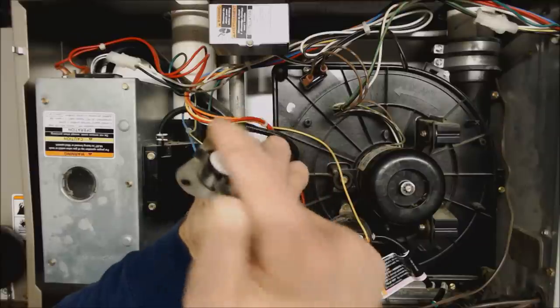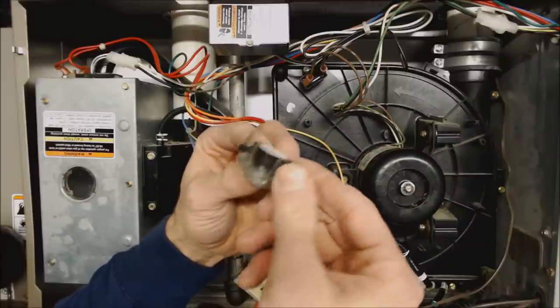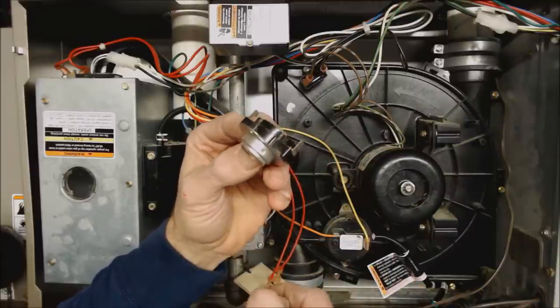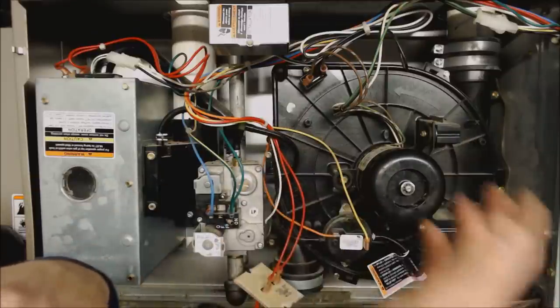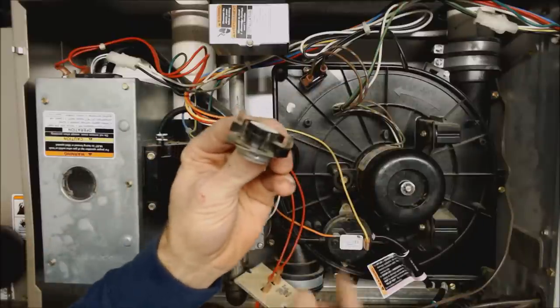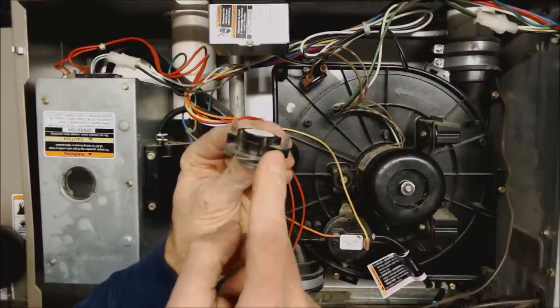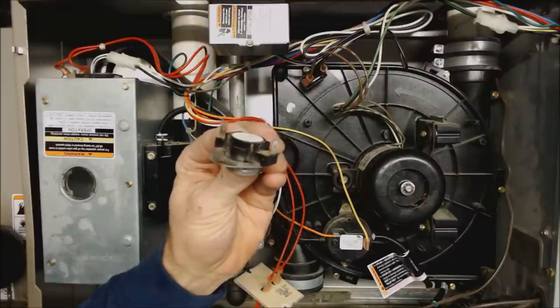If this switch is open, then it means that the furnace is overheated. And if that's the case, then either the gas is too high or the airflow is too low, or maybe just that this sensor is going bad. So you got to check those adjustments.